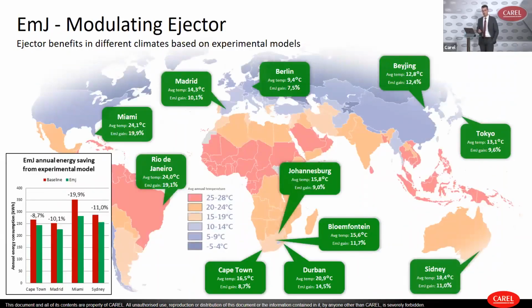This is an overview. As I told you before, the CAREL modulating ejector is a vapor ejector. So it means that the efficiency of this device will increase with the average temperature, with the climate profile and the average temperature that you will have in the country where you install the unit. So, for example, if we look at Miami or Rio de Janeiro, where the average temperatures are more than 20 degrees, you can have a saving of up to 20%. But if you look at Europe or South Africa or China, with a lower average temperature, around 10 degrees C, you can still have a good benefit in terms of energy saving, from 7 to 10 to 12%.